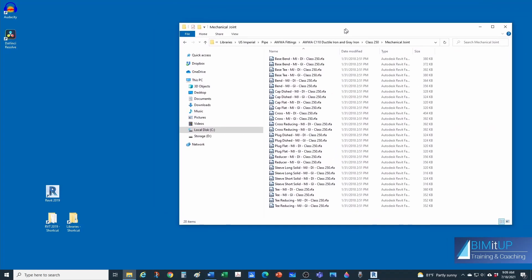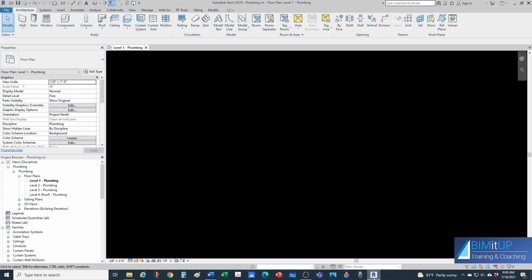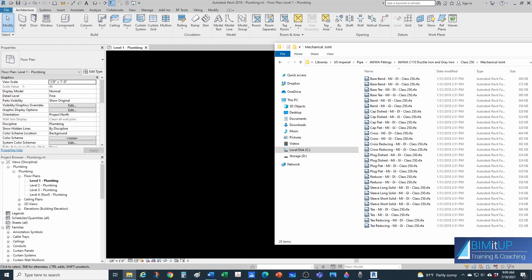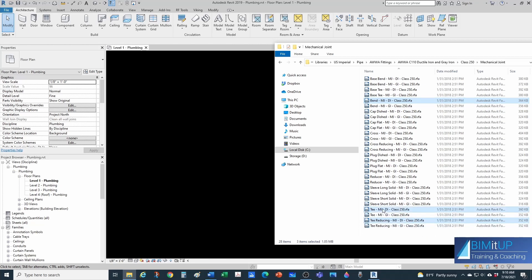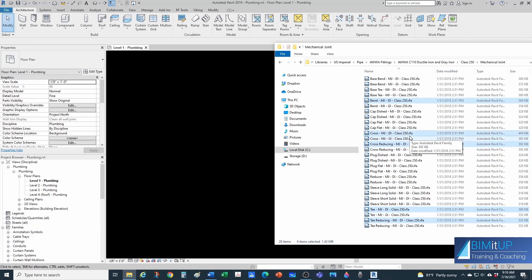I'm going to drop the fittings into my project at the same time. For our elbow, we're going to get a bend — Mechanical Joint Ductile Iron Class 250. For our junction, remember the rule of thumb on routing preferences: if you can find a reducing T, go ahead and get that one, and in addition get the standard T for sizes where you don't have a reducing T. Let's get both of those — again Mechanical Joint Ductile Iron Class 250. For our cross, we want to get the reducing and then get the standard.